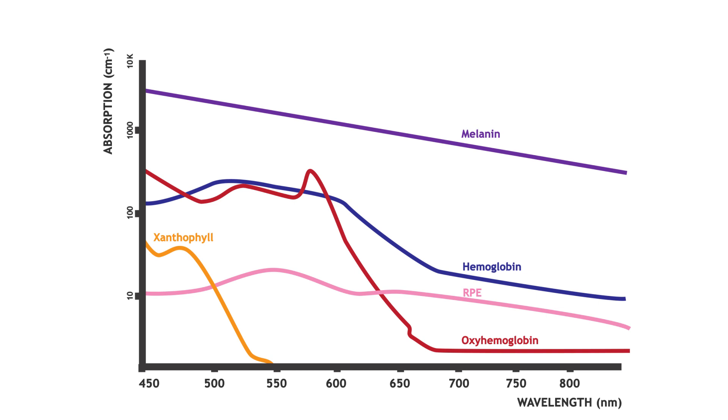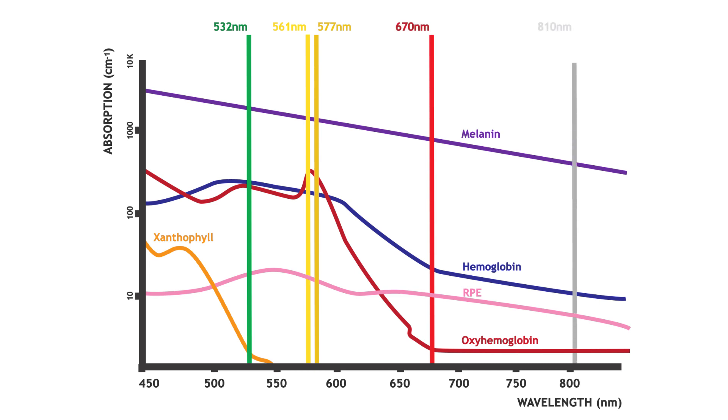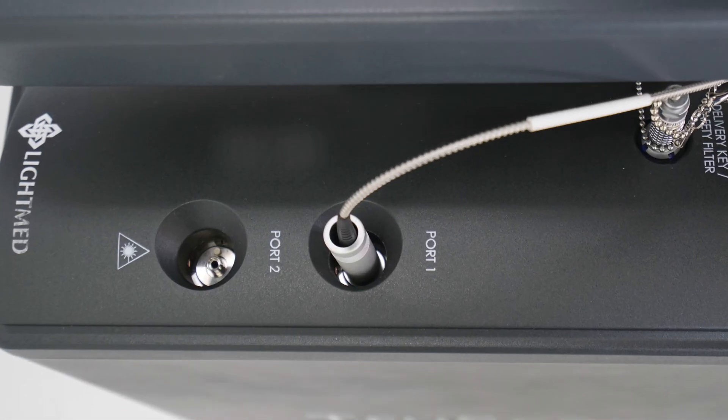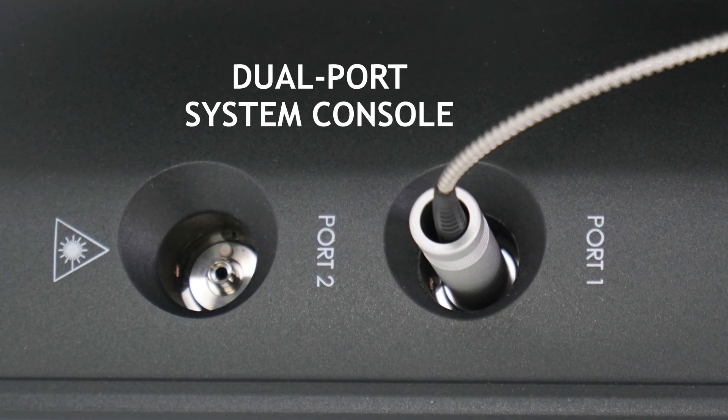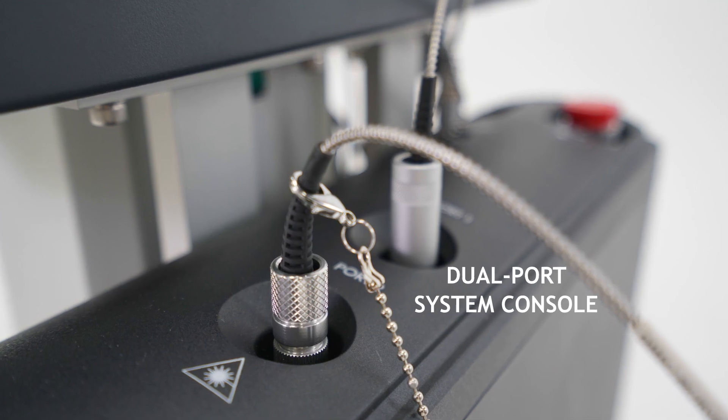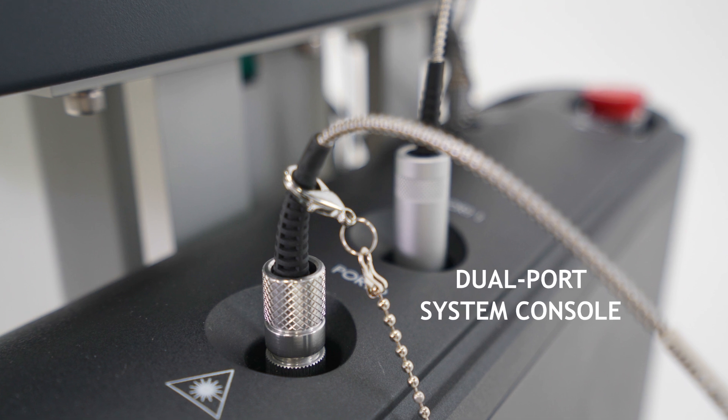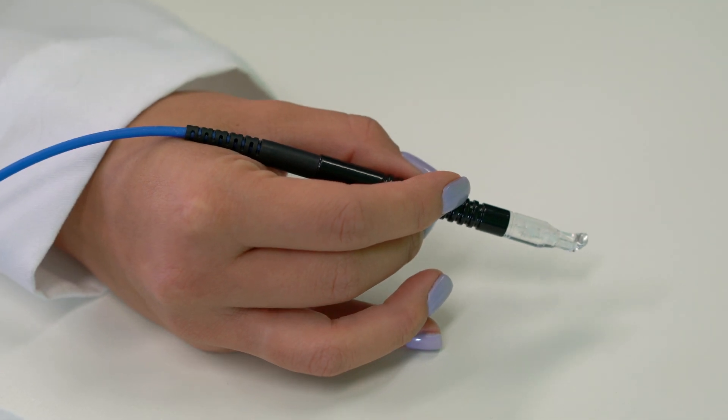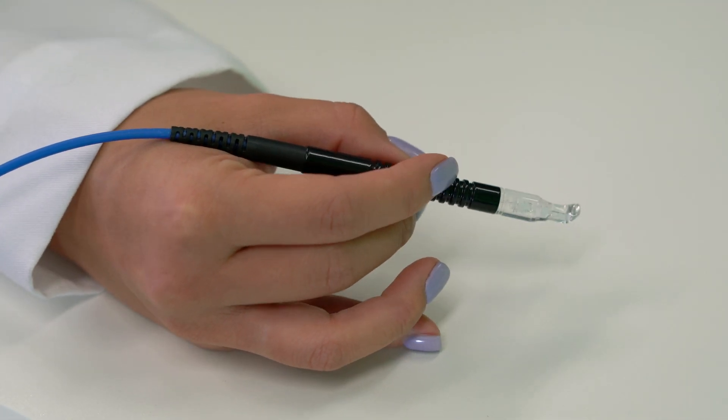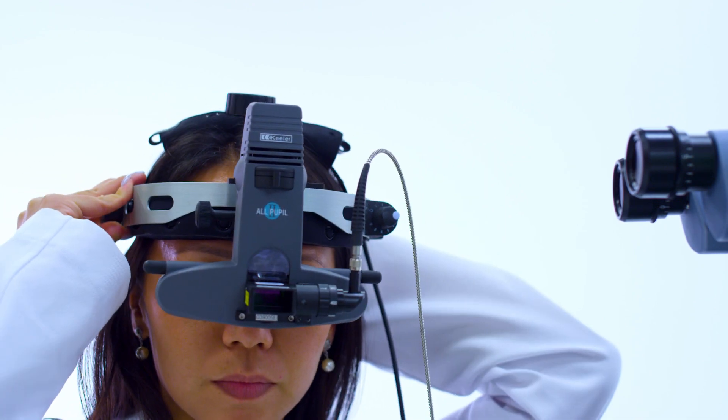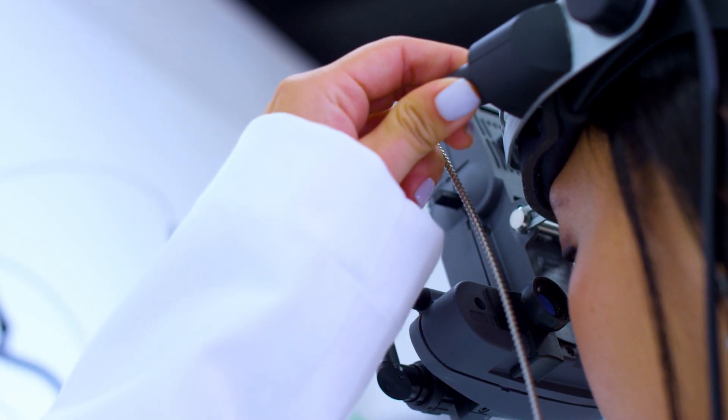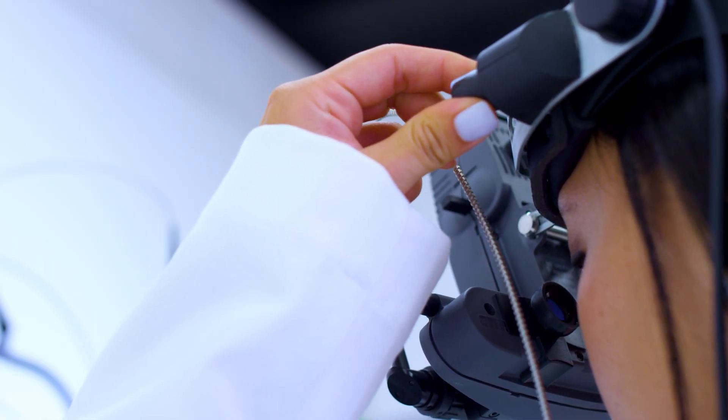The available wavelengths include the 532 nanometer green wavelength, the 561 or 577 nanometer yellow wavelength, the 670 nanometer red wavelength and the 810 nanometer infrared wavelength. The console is equipped with a dual port system allowing easy integration of additional delivery devices such as endo probes, glaucoma probe and single or multi-wavelength laser indirect ophthalmoscopes.